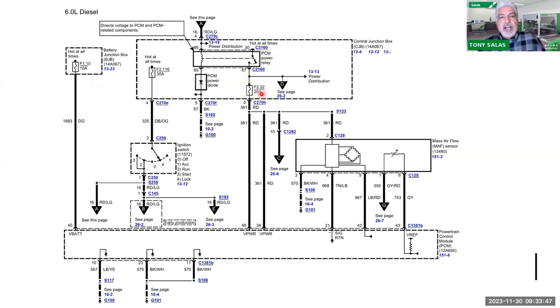What I'm going to do is see if I still have power there, and that tells me that the relay contacts are closed too as well. As a matter of fact, if I want to do a quick short test, let me redo this again. I could just go to fuse 2.22 and see, with the switch off, if there is power at that fuse as well. But again, understanding how the circuit works is key.